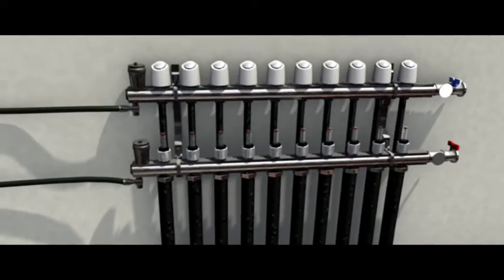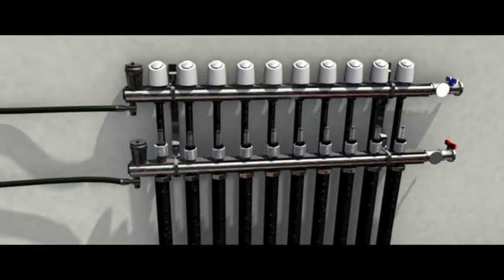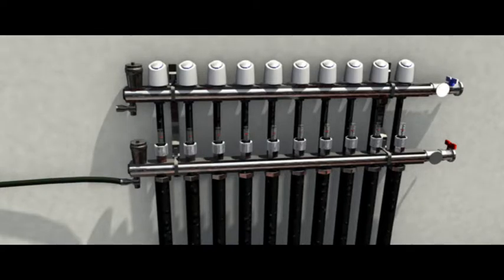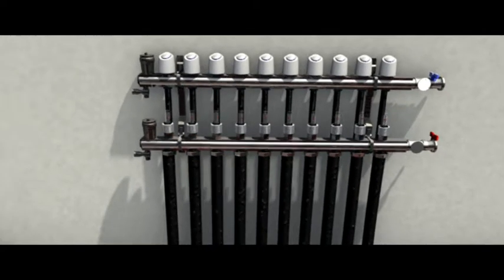To open the flow meters, slide the white plastic lock shield collar up and then turn fully counterclockwise. Water will now flow through that loop and out the drain valve of the return manifold into the bucket. This process should be repeated for all loops until water flows out the drain valve of the return manifold at full bore. Now that the system is filled with water, the drain valves can be closed and the hoses disconnected.